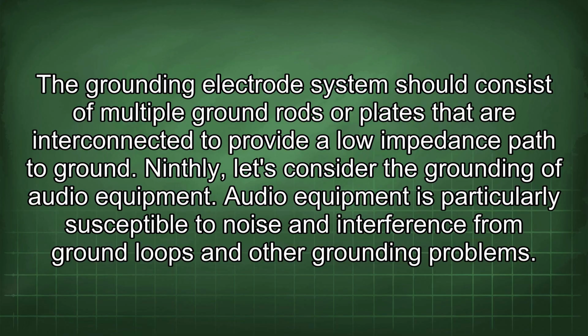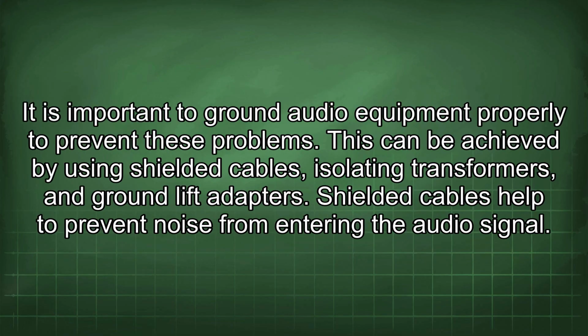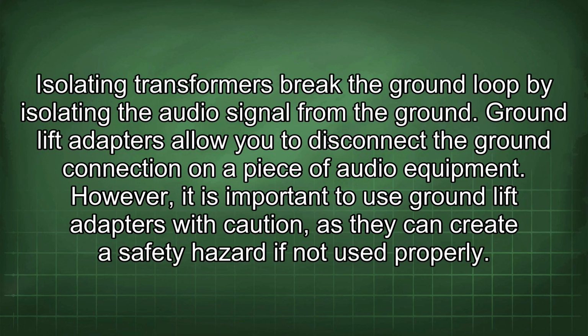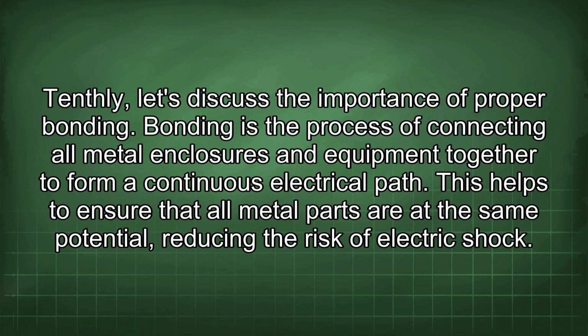Audio equipment is particularly susceptible to noise and interference from ground loops and other grounding problems. It is important to ground audio equipment properly to prevent these problems. This can be achieved by using shielded cables, isolating transformers, and ground lift adapters. Shielded cables help to prevent noise from entering the audio signal. Isolating transformers break the ground loop by isolating the audio signal from the ground. Ground lift adapters allow you to disconnect the ground connection on a piece of audio equipment. However, it is important to use ground lift adapters with caution, as they can create a safety hazard if not used properly. Tenthly, let's discuss the importance of proper bonding.